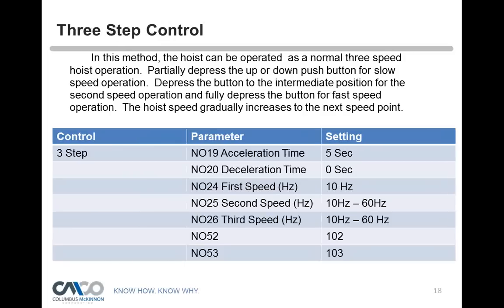For three-step control, NO52 goes to 102 and NO53 stays at 103, setting up three deep presses on the button. The hoist operates as a normal three-speed hoist. The first point can be as low as 2.67 feet per minute, the second speed anywhere in between, and the third speed up to 16 feet per minute. So you can configure one-step, two-step, or three-step control — equivalent to a single-speed, two-speed, or three-speed hoist.